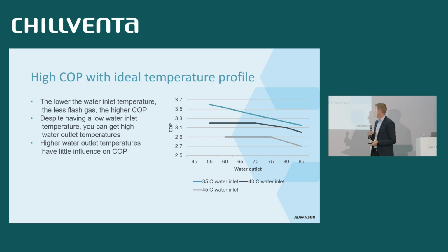For example, if we look at the black line on the graph here, the black line indicates 40 degrees water inlet. And then you see on the x-axis we have the water outlet temperature. So if we are to supply 55 degrees supply temperature or 70 degrees supply temperature, the COP doesn't change. So we can actually achieve high supply temperature without compromising the COP. Even up to 80 degrees, you can see there's a slight decrease in the COP, but still we can provide really high supply temperature with only small sacrifice on the COP. The two other lines here, the blue one at the top is similar. It indicates 35 degrees water inlet, and the gray one at the bottom is 45. But the picture is more or less the same.